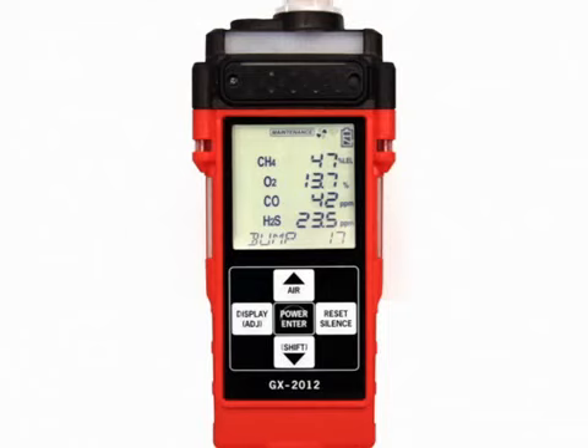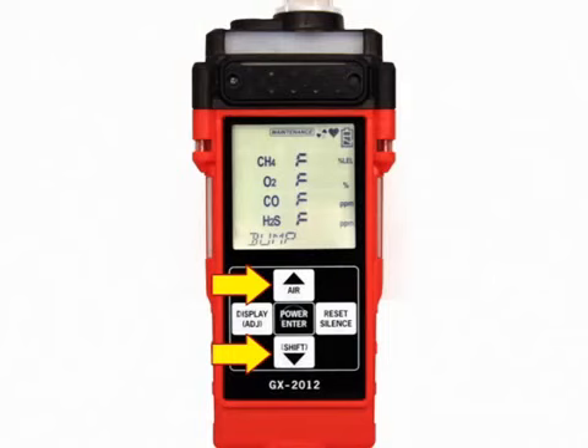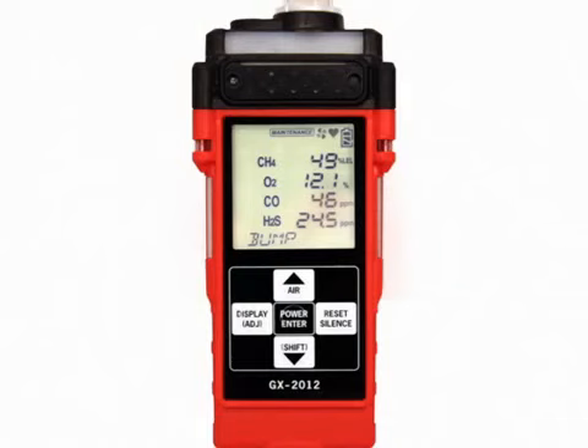When Auto Cal in the Bump Set menu item in maintenance mode is set to off, the instrument will indicate which channels passed or failed the bump test with a P, pass, or an F, fail, to the right of the gas. To view the bump test gas readings, press the Air or Shift button. You can scroll between the bump test results and the bump test gas readings with the Air or Shift buttons. To return to the bump screen in calibration mode, press the power enter button. If bump test fails, perform a calibration.